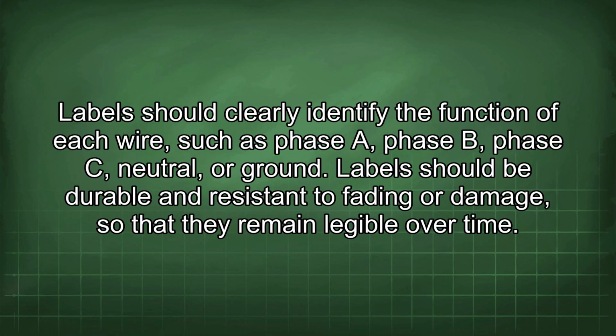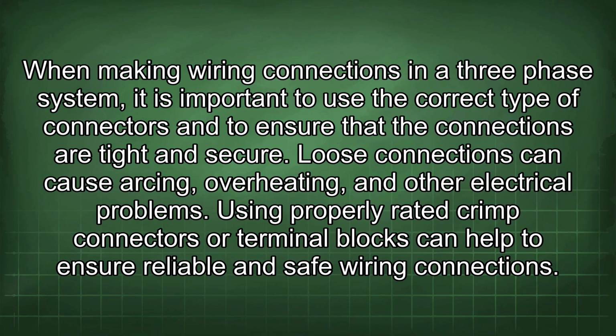Labels should clearly identify the function of each wire, such as phase A, phase B, phase C, neutral, or ground. Labels should be durable and resistant to fading or damage so that they remain legible over time. When making wiring connections in a three-phase system, it is important to use the correct type of connectors and to ensure that the connections are tight and secure. Loose connections can cause arcing, overheating, and other electrical problems. Using properly rated crimp connectors or terminal blocks can help to ensure reliable and safe wiring connections.